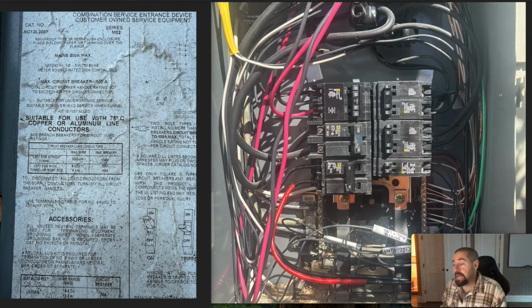So as a hot bus panel pertains to solar and storage, connecting a breaker on this panel, a lot of people get mixed up. You know, they think of a backfed breaker. They'll see that, hey, this is a 200 amp panel. I'm trying to connect a backfed breaker, and they'll go to that backfed breaker rule thinking they're limited to a 40 amp backfed breaker, but that couldn't be further from the truth.